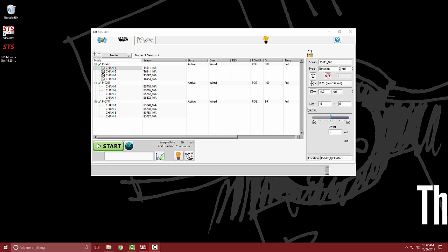Hello, this is Jason with BDI, and in this video I'm going to show you how to import a calibration file into STS-LIVE. So as you can see here, I've started STS-LIVE. I've got 3 nodes that are checked in, and I have sensors plugged into all 3 of the nodes.